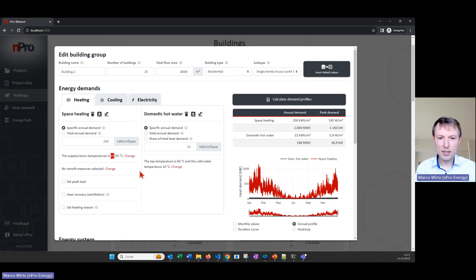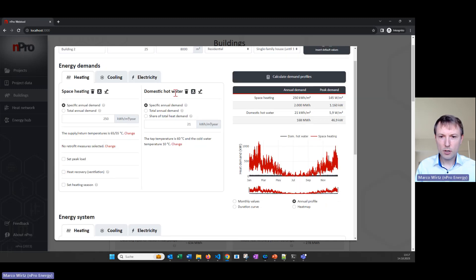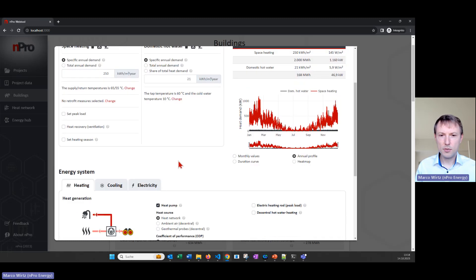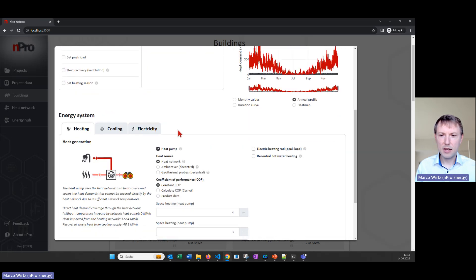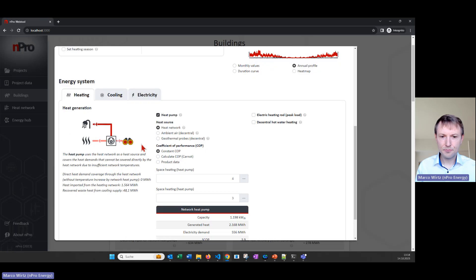Here we have 65°C for covering the space heating demands, which depends on the building type — lower for modern buildings, possibly higher for older ones. For domestic hot water we also have a supply temperature of 60°C. That's important because the network is at around 10°C, and we need to boost the temperature in the building to reach those supply temperatures. We click on the heating part of the energy system and see that a heat pump is being used.